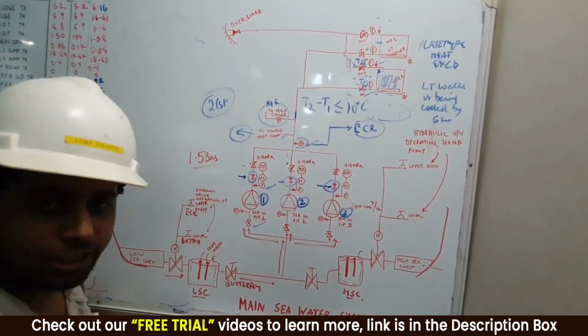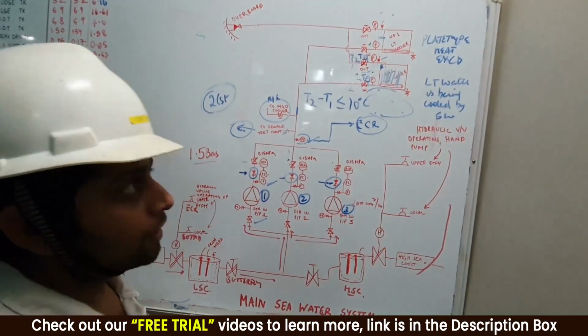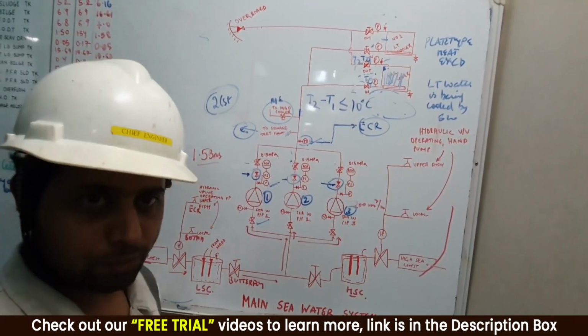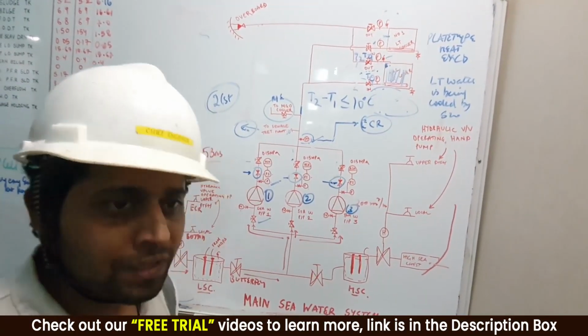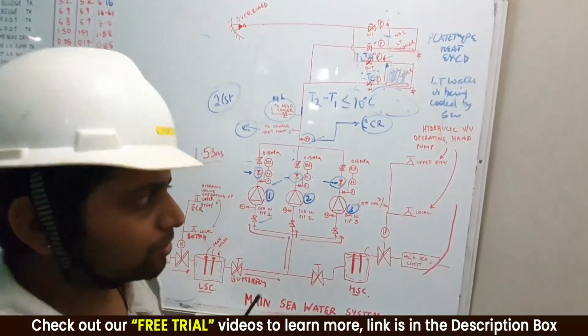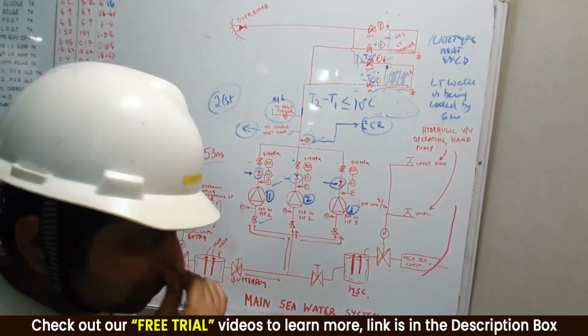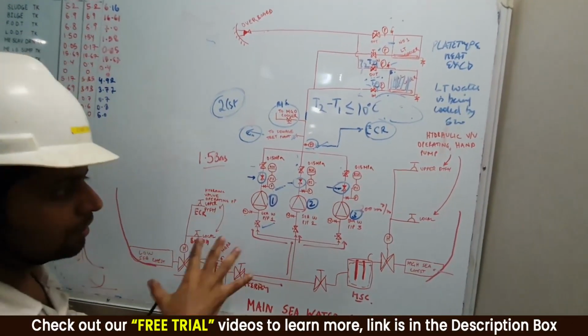You have to open this huge LT cooler. Over here on my ship, we have got 150 plates fitted in. It takes approximately 2 to 3 days to clean an LT cooler. It's a 6-monthly routine on board our ship. So guys, this is something which is very, very important for you guys to know. I hope you have understood this system over here.